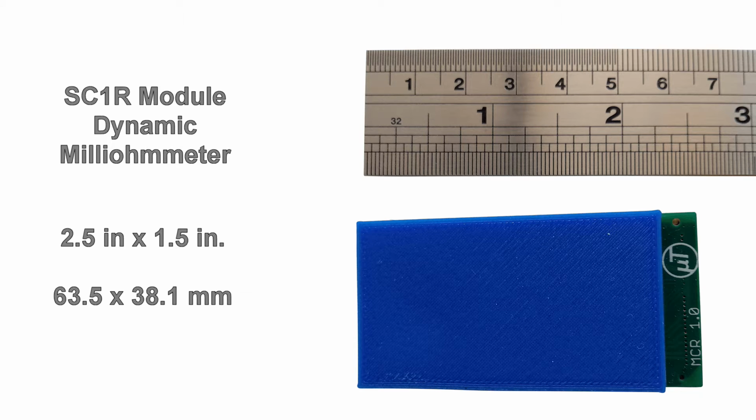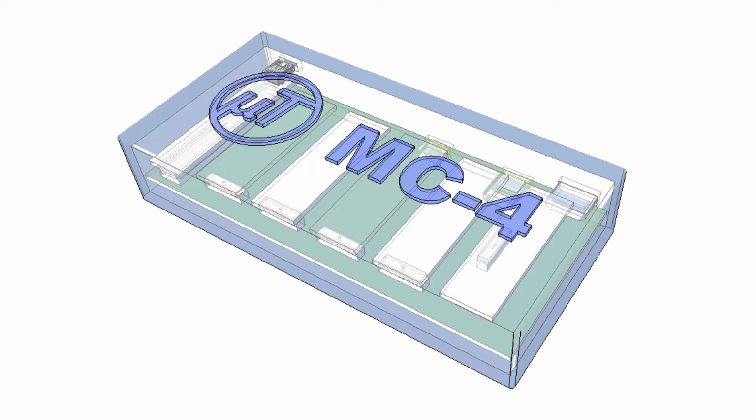This is a single-channel dynamic Milliohmmeter module. It mounts onto the MCX motherboard. The modular architecture minimizes downtime in production. In the rare event that a module fails, you can quickly replace it and recalibrate the instrument.